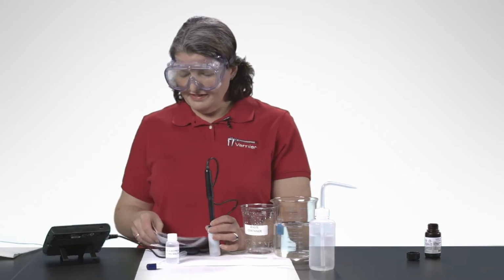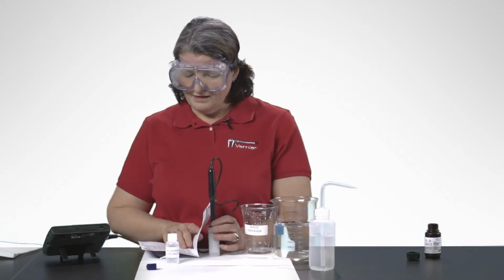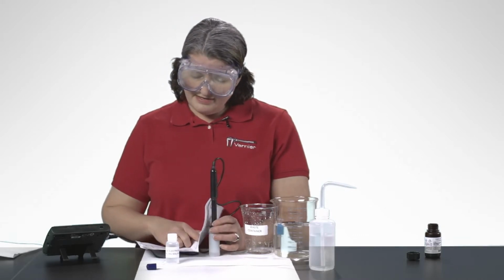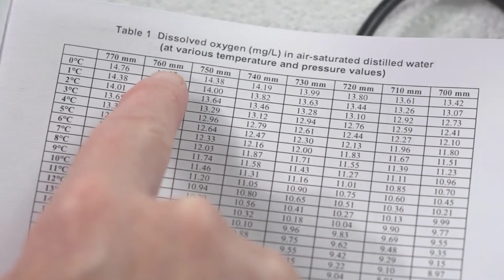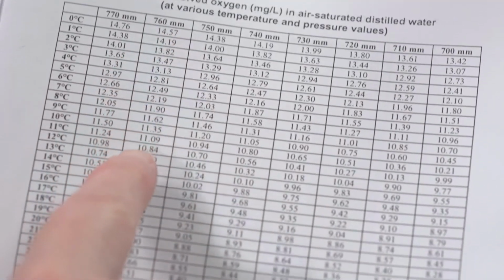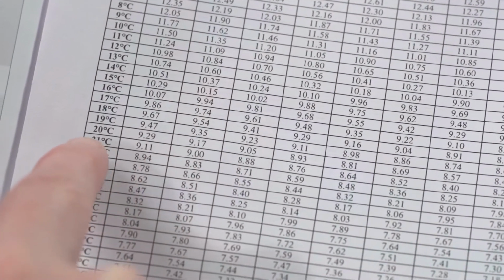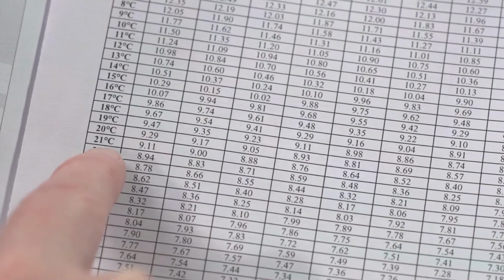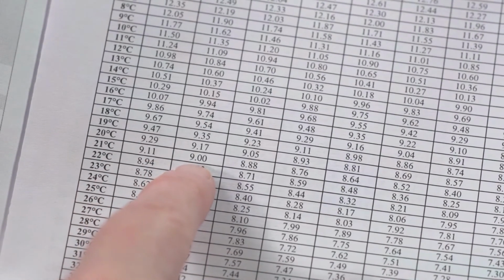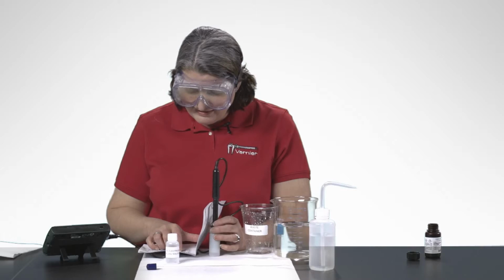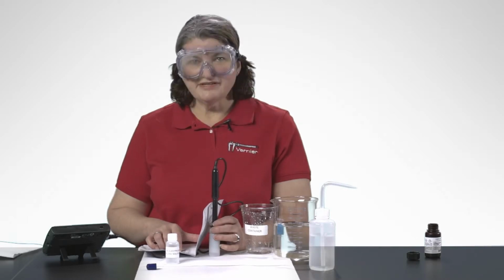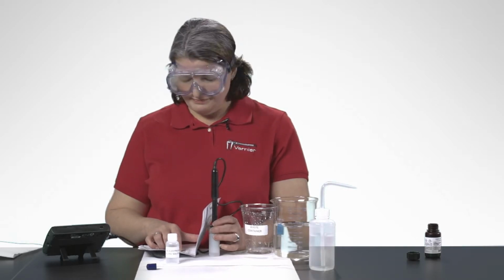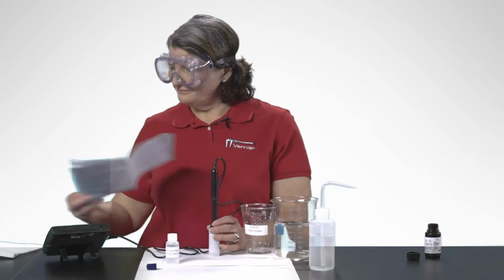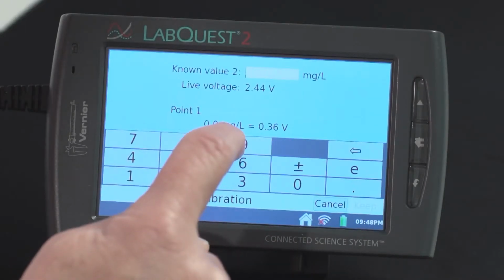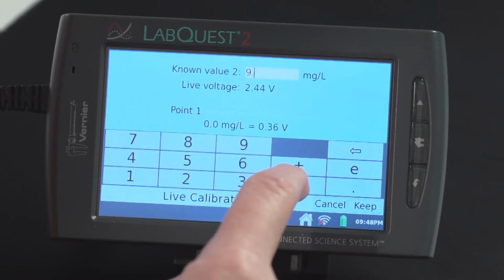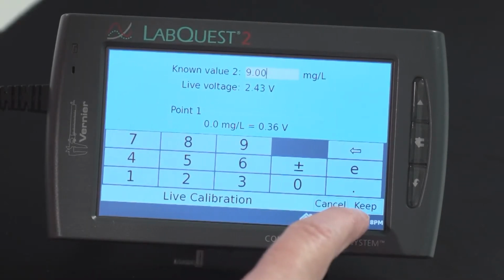So I open up to that chart, and I find that at this pressure, which is 760 millimeters, I measured that before we started, and the temperature, which I know it is in the room, which is 21 degrees, we have exactly 9.00 for our milligrams per liter. So that's what I put here, 9.00. And keep that.